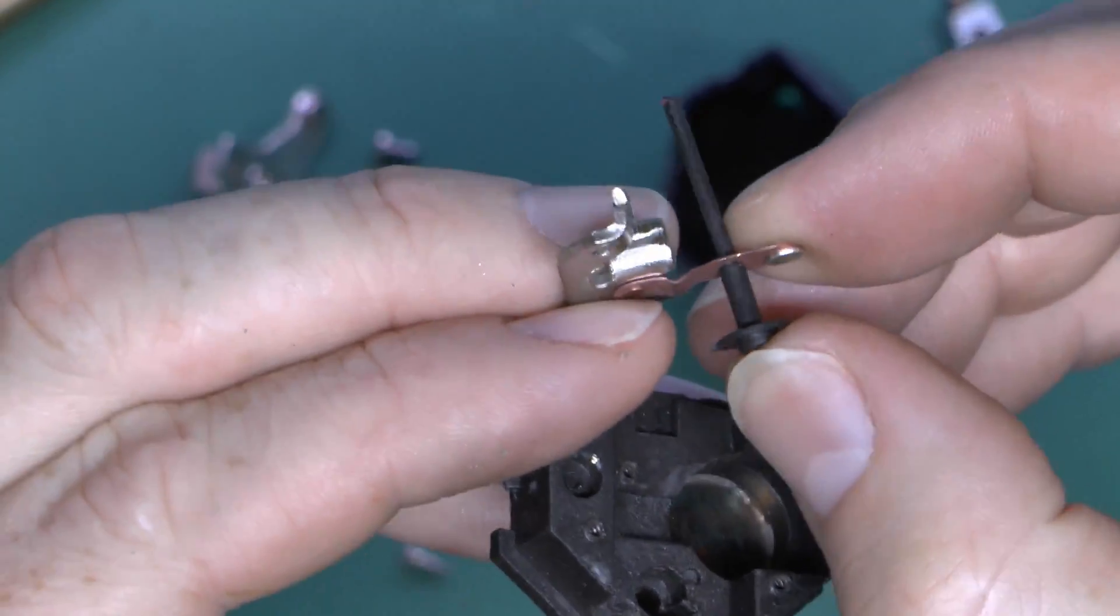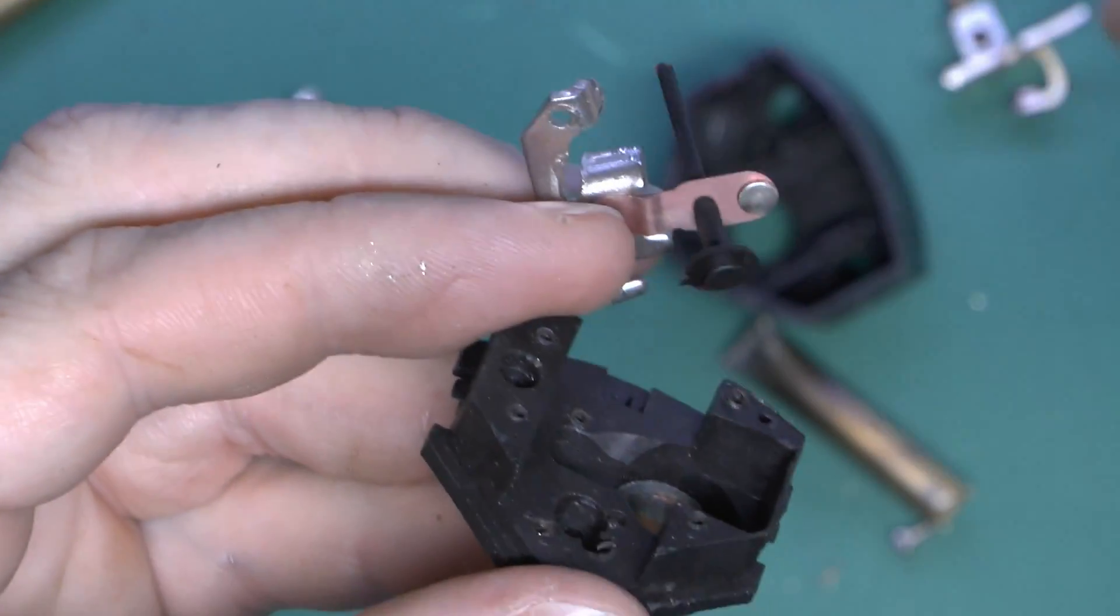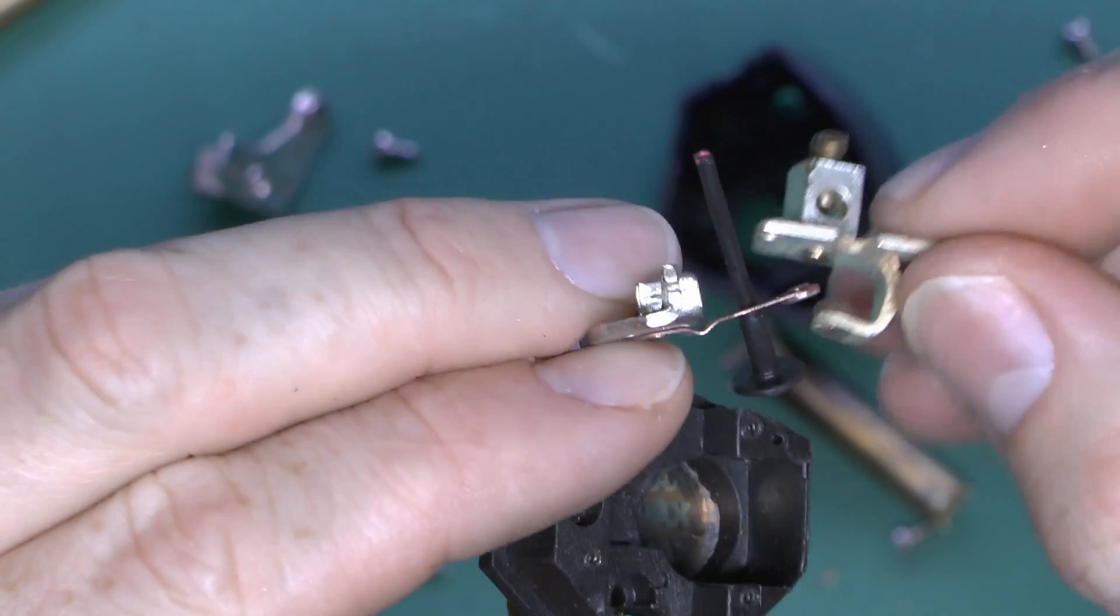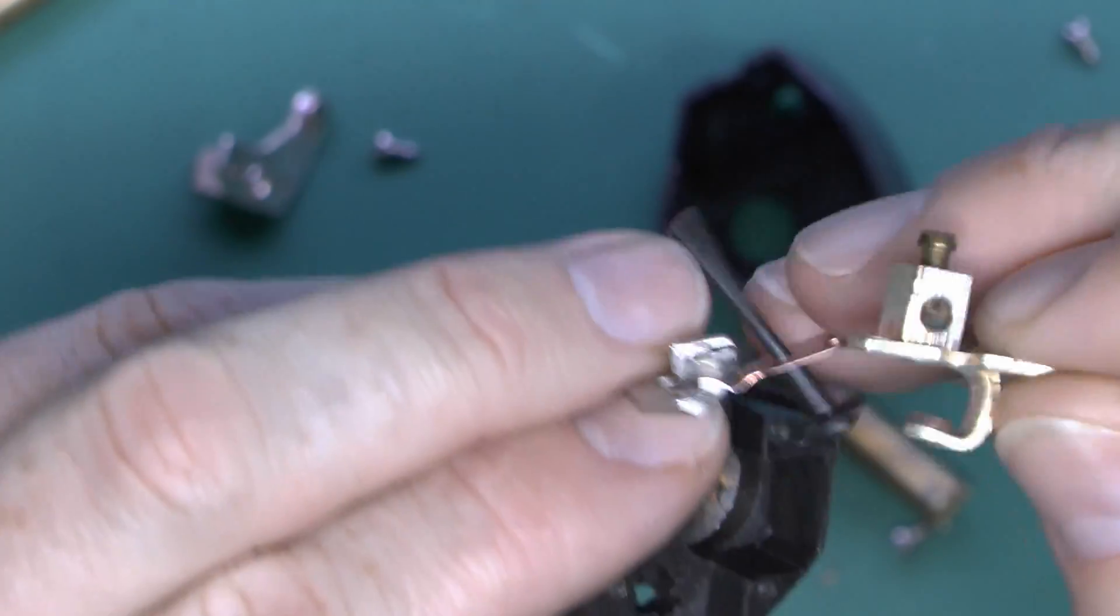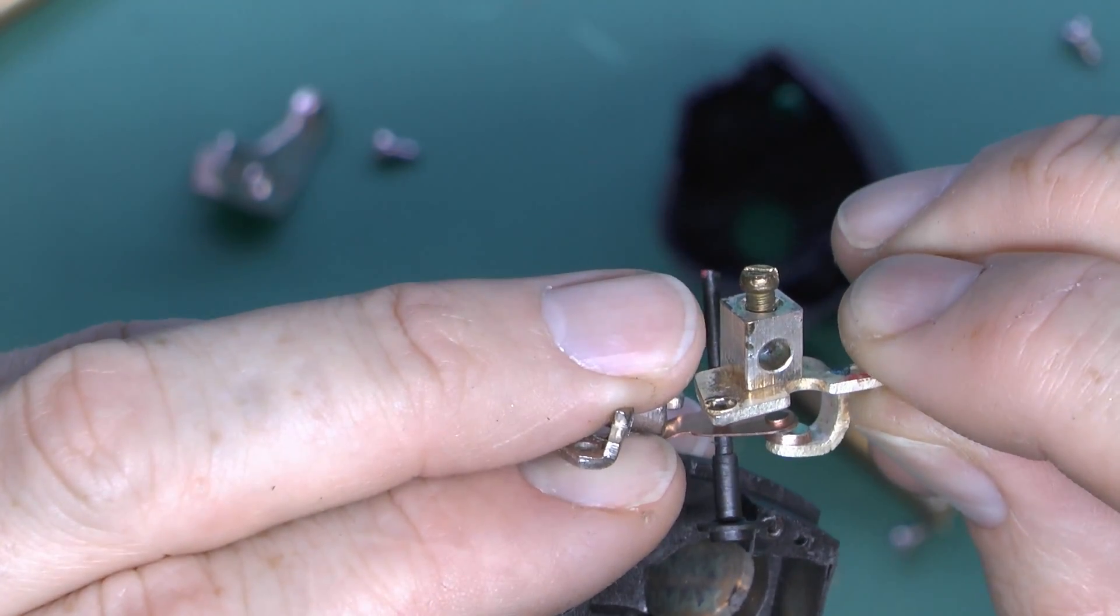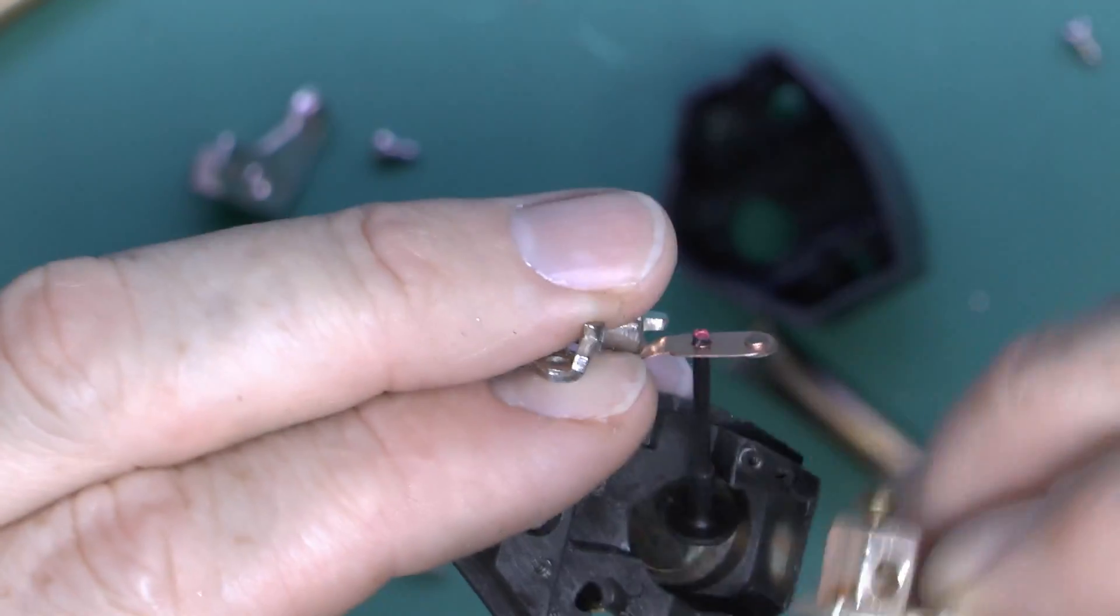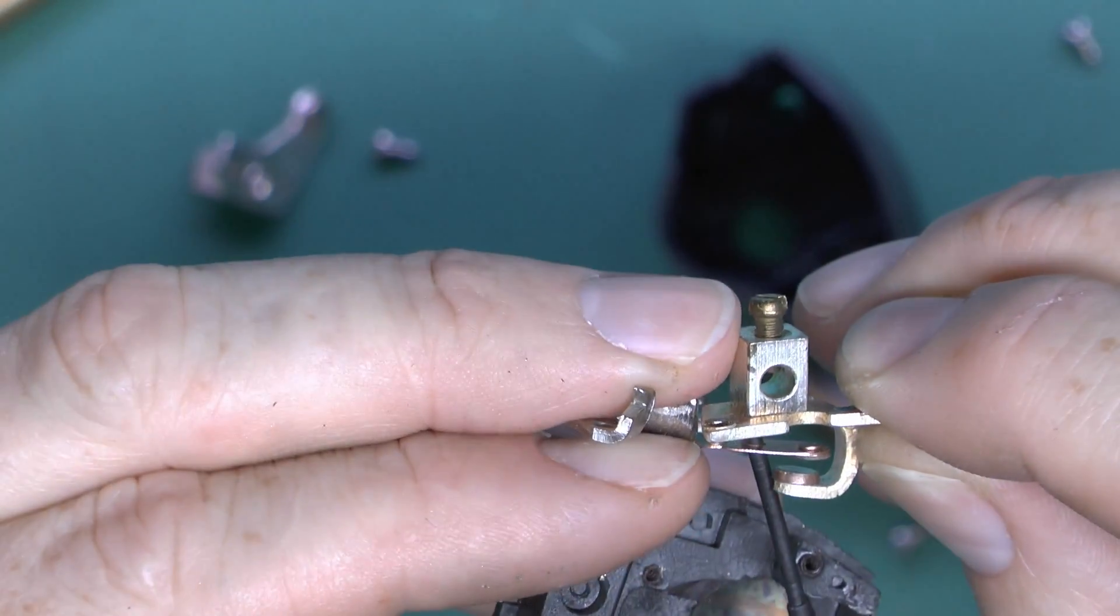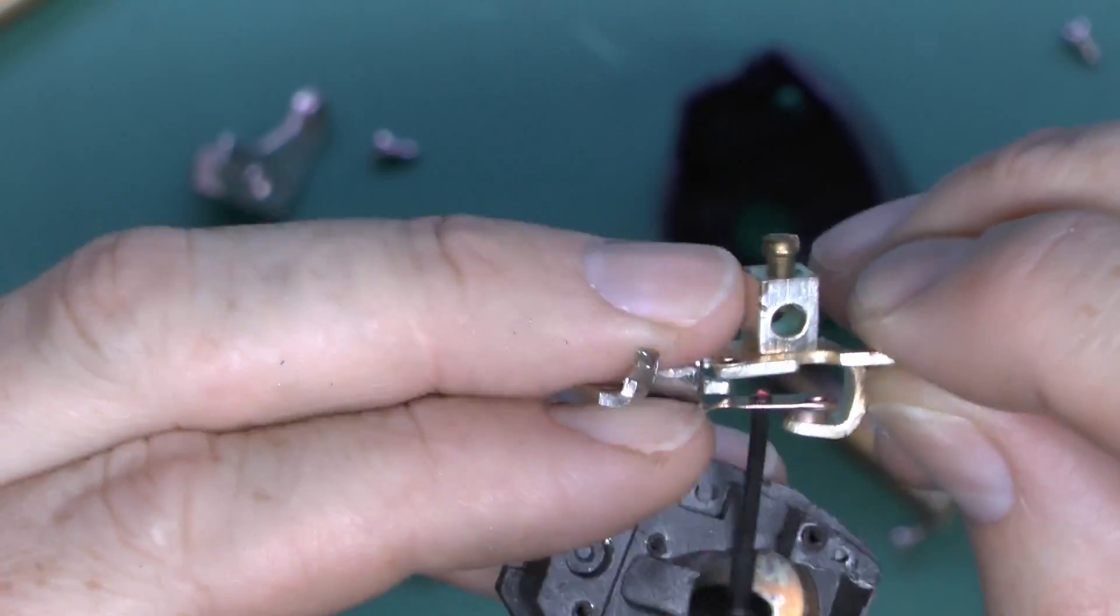Here's the little reset plunger, and that's one side of the overheat contact, and then here's the other side on the other contact. So that would normally be in the closed position. So you'd have that just pressing onto that. And then in the event of it overheating, this will lift and then provide that extra gap there. So of course, it's now in the open position.